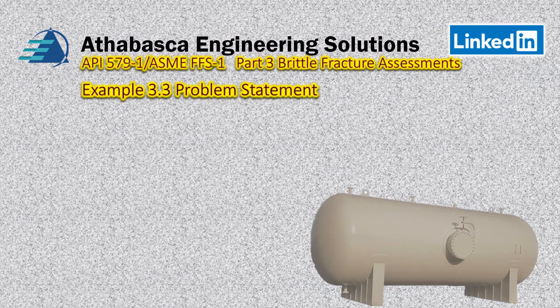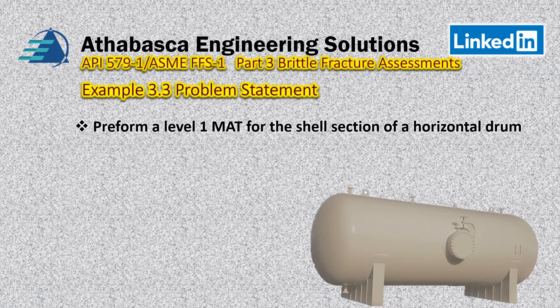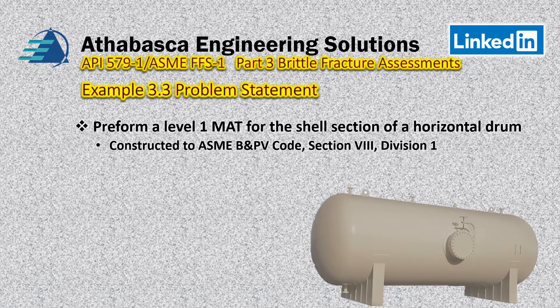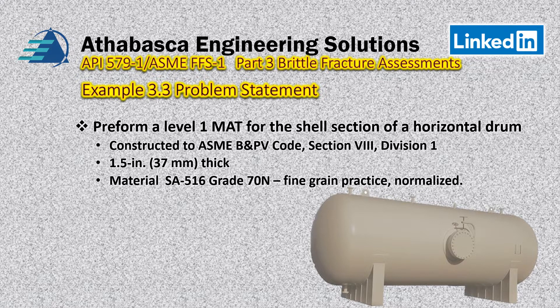In this particular example, we're going to be looking at a level one MAT, which is a minimum allowable temperature for this material. In particular, we're just going to look at the shell section, so we don't have to get into the issues of governing thickness because the governing thickness is the thickness of the shell. It's just for a horizontal drum, and it's constructed to ASME Section Eight Division One of the boiler pressure vessel code. It's one and a half inches thick, or 37 millimeters, and the material of construction is SA 516 Grade 70N, which is fine grain practice and it's normalized.